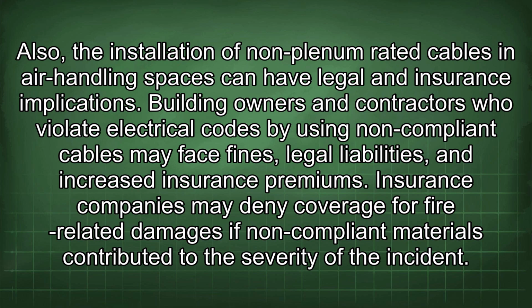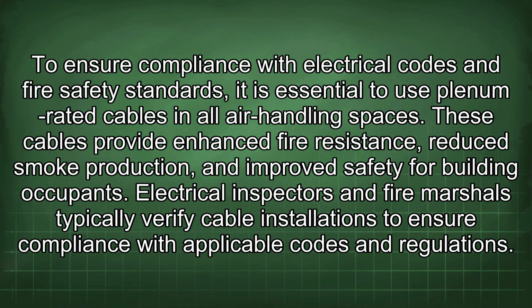Also, the installation of non-plenum rated cables in air handling spaces can have legal and insurance implications. Building owners and contractors who violate electrical codes by using non-compliant cables may face fines, legal liabilities, and increased insurance premiums. Insurance companies may deny coverage for fire-related damages if non-compliant materials contributed to the severity of the incident. To ensure compliance with electrical codes and fire safety standards, it is essential to use plenum-rated cables in all air handling spaces. These cables provide enhanced fire resistance, reduced smoke production, and improved safety for building occupants. Electrical inspectors and fire marshals typically verify cable installations to ensure compliance with applicable codes and regulations.